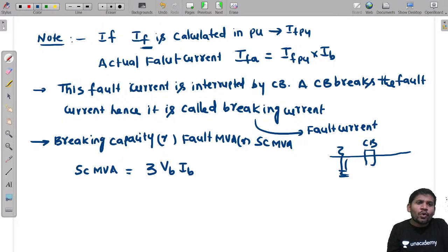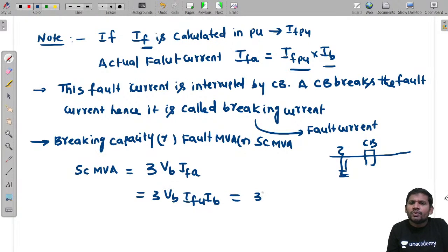But sir, this is not the base current. It is the breaking current, the actual fault current, I_FA. But I want to write this 3 V_B in terms of per unit current, sir. In terms of per unit current means I_FU into I_B, sir. So shall we write like this: 3 into V_B into I_B, that is I_FU, per unit current. But 3 into V_B I_B is the base MVA, sir.